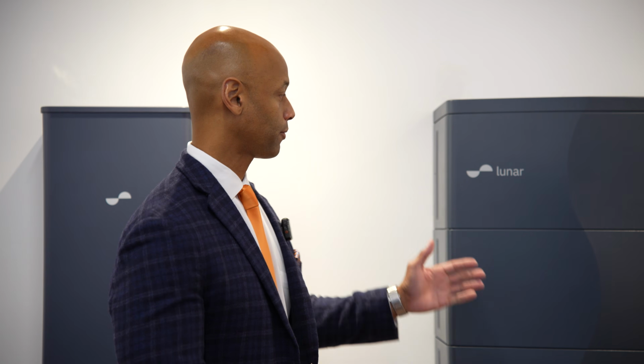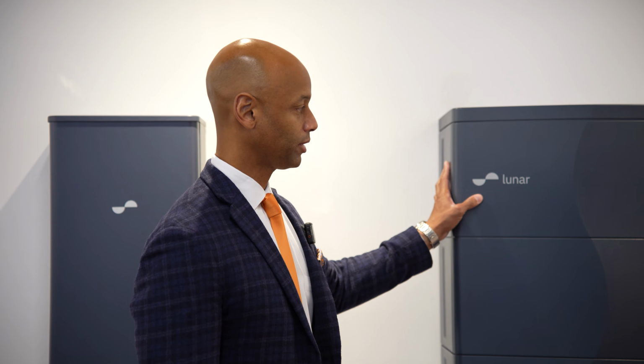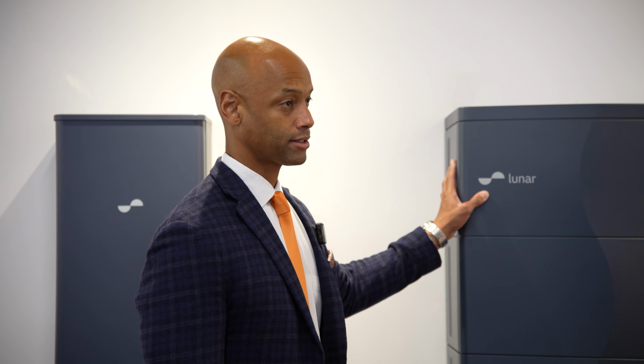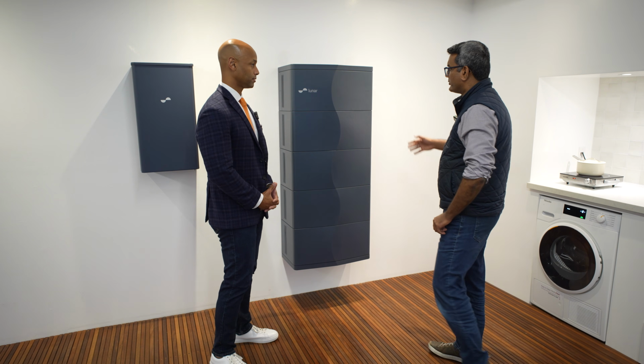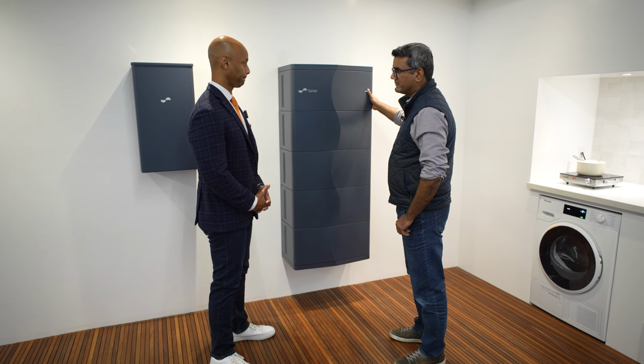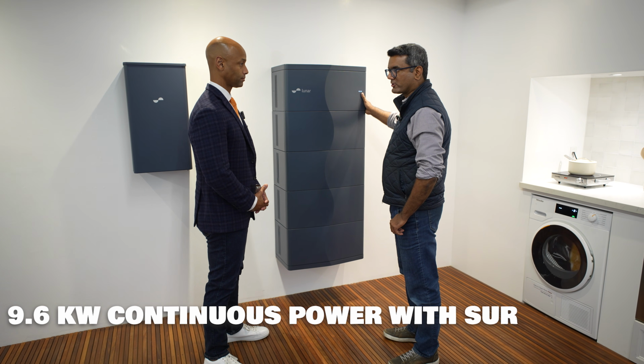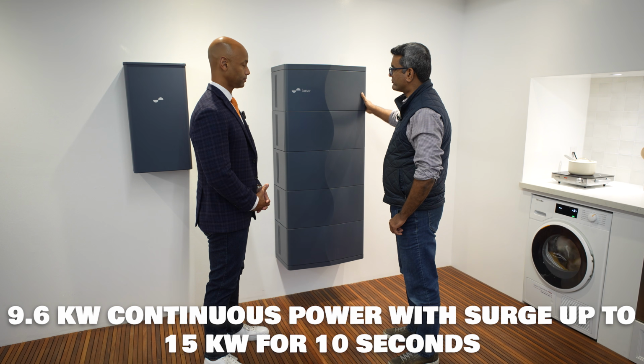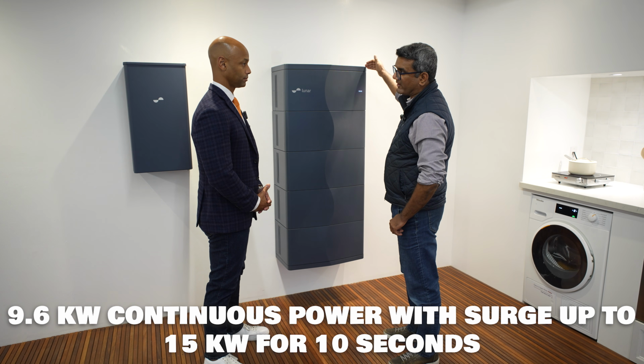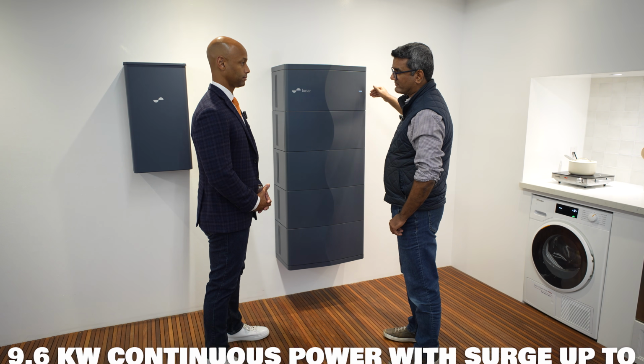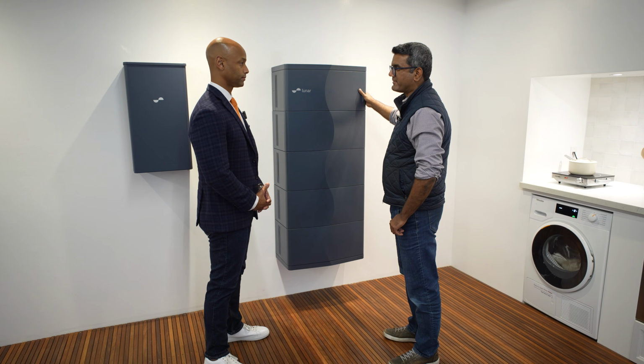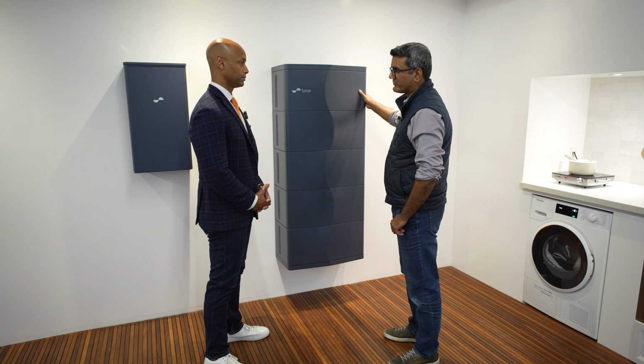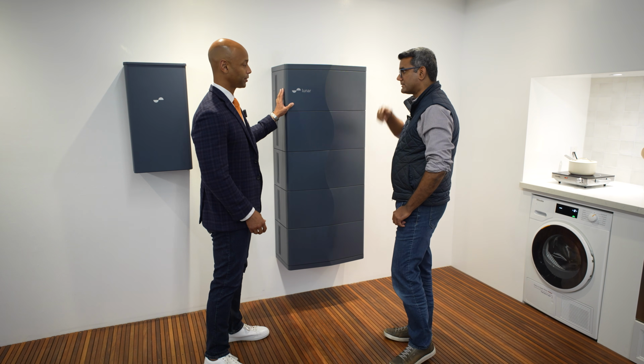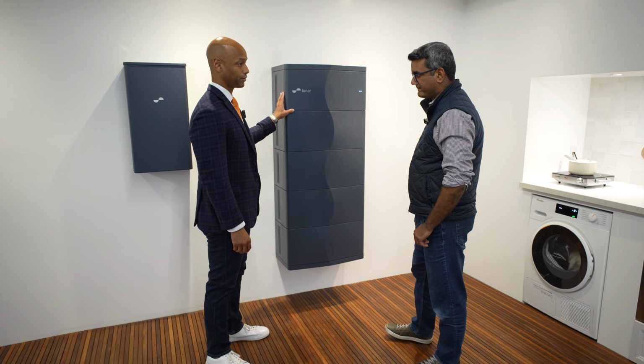So Kunal, give me a rundown on the technical specs of the unit, starting with the inverter at the top. What are we looking at in terms of power capacity? This is a 9.6 kilowatt inverter, goes on a 50 amp breaker, with a surge capacity of 15 kilowatts for about 10 seconds, and a continuous max power of 9.6 kilowatts.